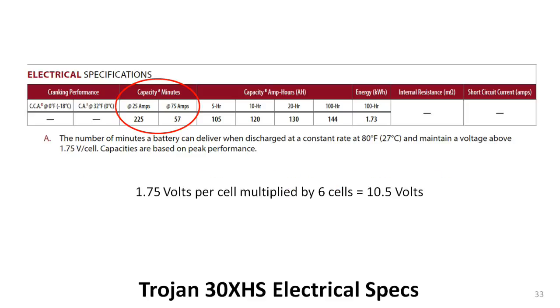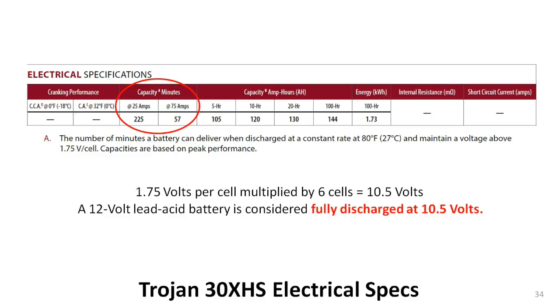A 12-volt lead-acid battery has six cells connected in series, so multiplying 1.75 volts times six gives the voltage at which the battery is completely discharged — 10.5 volts. That applies to all 12-volt lead-acid batteries, not just this particular Trojan. Most people don't know this fact; they mistakenly think that any voltage above zero means the battery still has usable power, which is completely wrong. Please hold on to that fact because it will come up again and again as you learn more about lead-acid batteries.